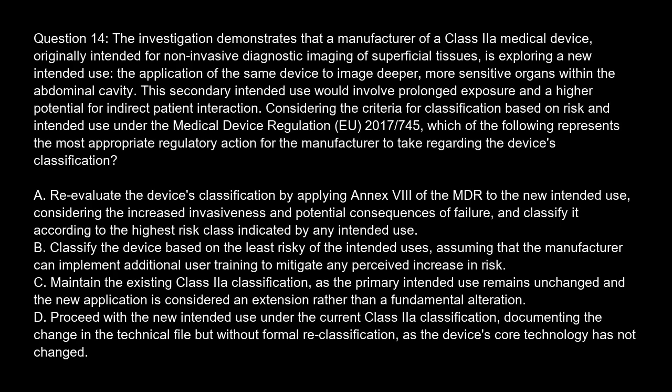Question 14. The investigation demonstrates that a manufacturer of a Class IIa medical device, originally intended for non-invasive diagnostic imaging of superficial tissues, is exploring a new intended use: the application of the same device to image deeper, more sensitive organs within the abdominal cavity. This secondary intended use would involve prolonged exposure and a higher potential for indirect patient interaction.